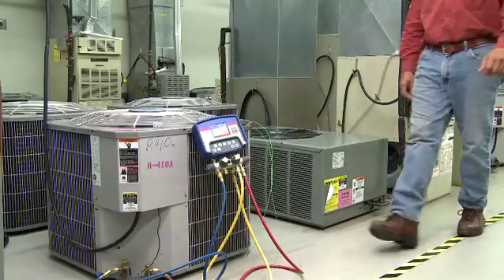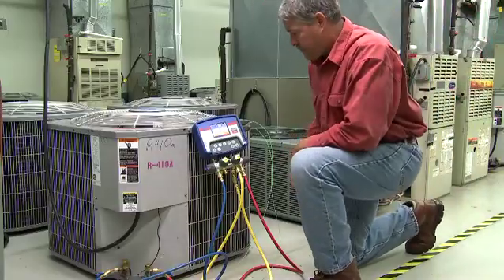The Yellow Jacket Refrigeration System Analyzer displays a chart of pressure over time, which comes in handy for viewing real-time activity in the system. I'm going to walk through different conditions you might encounter on the job so you can see how beneficial the charted pressures are in servicing equipment. In this setup, the analyzer is connected to a normal running R410A split system with expansion valve.